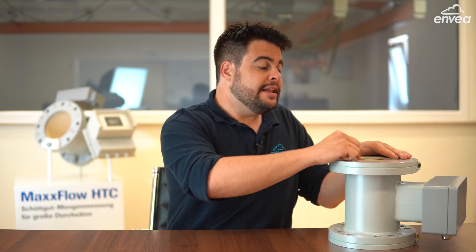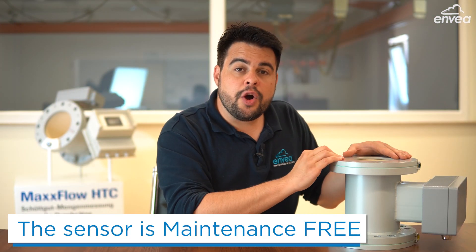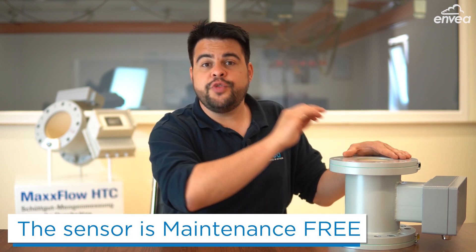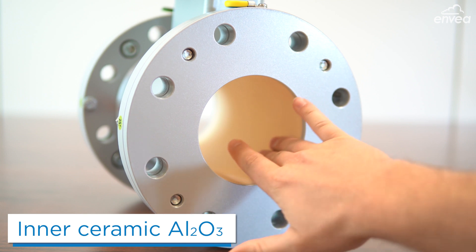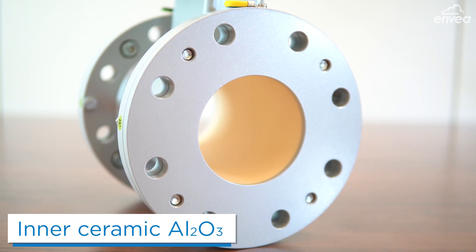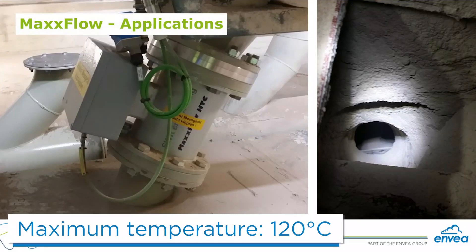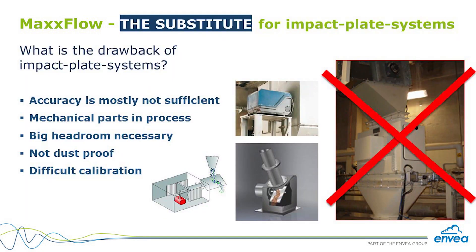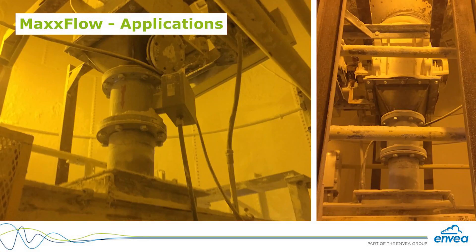Let's do a short recap. The sensor has no mechanical parts inside — no moving parts — which means it's maintenance free. The sensor has a ceramic inlay, meaning no problems with abrasion. The sensor can be used in applications up to 120 degrees Celsius. The sensor is small and can be fitted in tight spaces. Impact plates are something from the past — MaxxFlow is an impact plate killer. And MaxxFlow is dustproof.